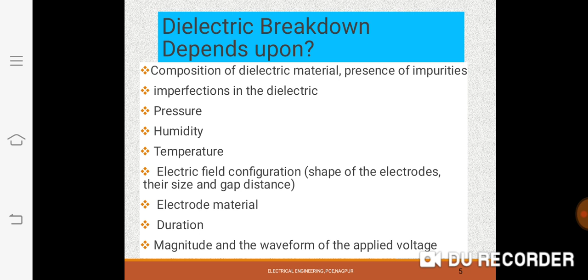Now what are the factors on which dielectric breakdown depends? It depends upon the composition of dielectric material, presence of impurities, imperfection in the dielectric. Then it also depends upon the pressure, humidity, temperature. It also depends upon the electric field configuration, shape of the electrodes, their size and gap distance. It also depends upon the electrode material and the duration for which the voltage stress is applied. It also depends upon the magnitude and wave shape of the applied voltage, meaning whether it is AC, DC, surge impulse or lightning impulse.